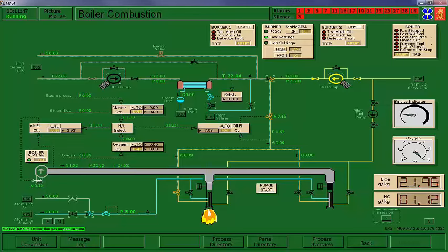This meter won't indicate until that gets below 5. We seem to have a stable flame. And I'm settling out somewhere around 3 or 4. Right now it's at 4% oxygen. Perfect. We've got a stable flame. We can now move on.